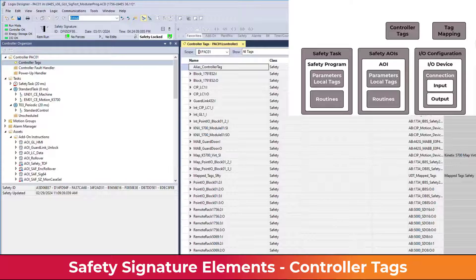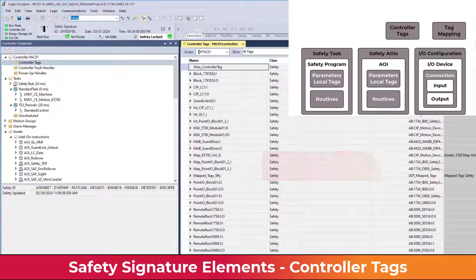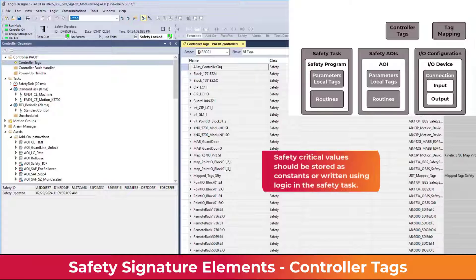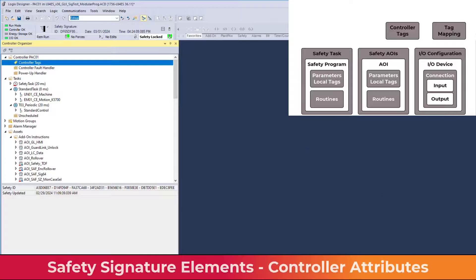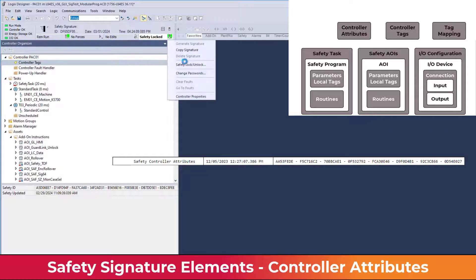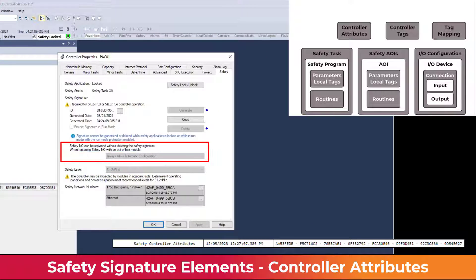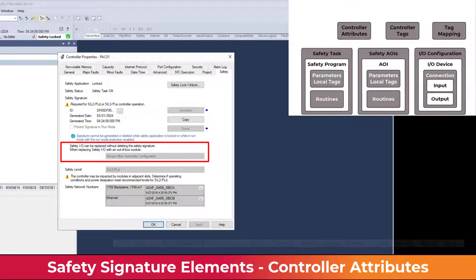The value of a tag is not part of the signature unless the tag is declared a constant. Safety critical values should be stored as constants or written using logic in the safety task. Controller attributes represent the controller configuration in the Controller Properties' Safety tab. This includes SIL configuration, Safety IO replacement configuration, and the run mode safety signature protection.